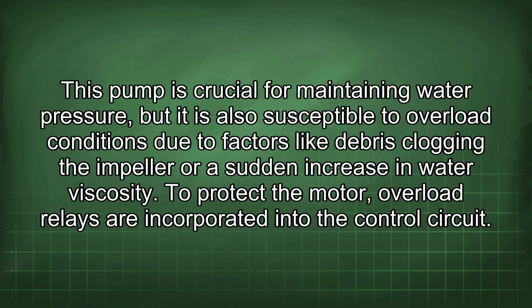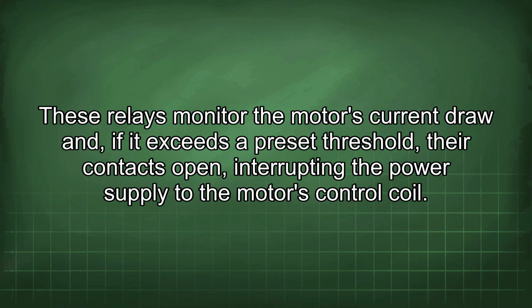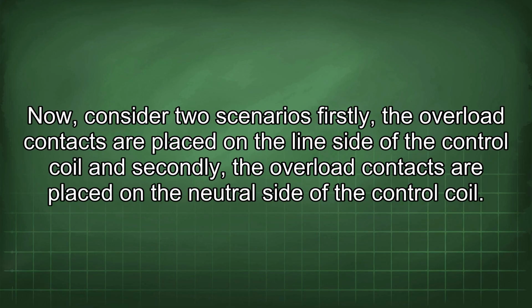This pump is crucial for maintaining water pressure, but it is also susceptible to overload conditions due to factors like debris clogging the impeller or a sudden increase in water viscosity. To protect the motor, overload relays are incorporated into the control circuit. These relays monitor the motor's current draw and, if it exceeds a preset threshold, their contacts open, interrupting the power supply to the motor's control coil. Now consider two scenarios. Firstly, the overload contacts are placed on the line side of the control coil, and secondly, the overload contacts are placed on the neutral side of the control coil.